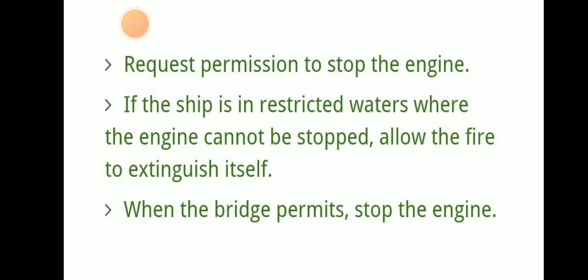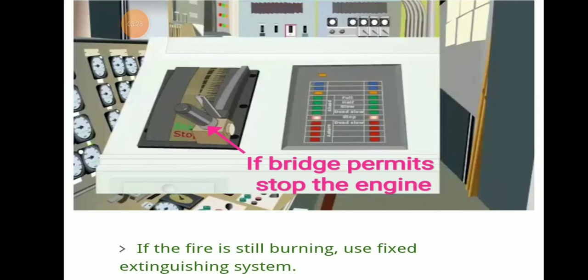Request permission from the bridge to stop the engine. If the ship is in restricted waters where the engine cannot be stopped, allow the fire to extinguish itself by reducing speed. If it is a small fire, it will automatically extinguish. Once the bridge permits, stop the engine.